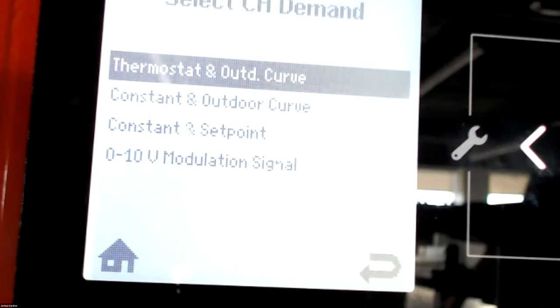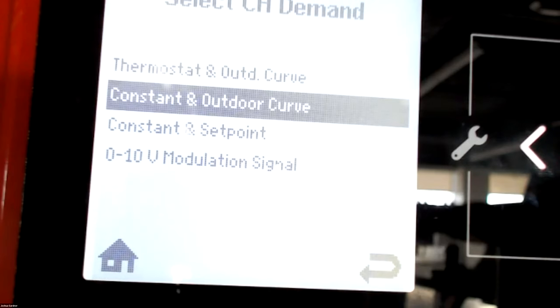The thermostat and outdoor curve, that means the system is going to sit cold until a thermostat calls, and then it's going to target whatever our curve design is. Constant and outdoor curve means this boiler 24/7, 365 is going to run at whatever our target on our outdoor curve is. So where you'd use this, I don't know if you guys are doing constant circ, but Europe is big. If you're using panel radiators with TRV vents and you design it with a temp and an outdoor curve, the thing just runs constantly. And as it calls for heat, it opens up the TRVs and they send heat through the radiators. So that's kind of where you'd use that.